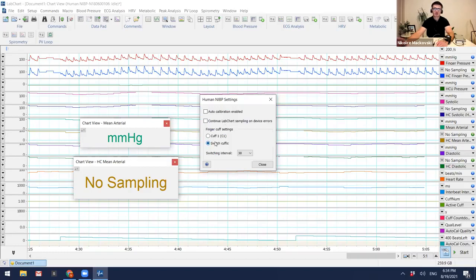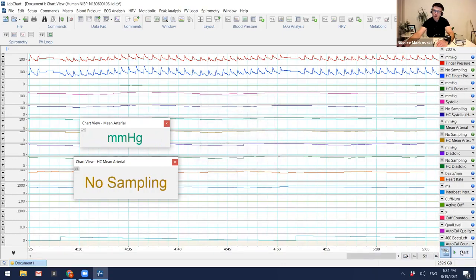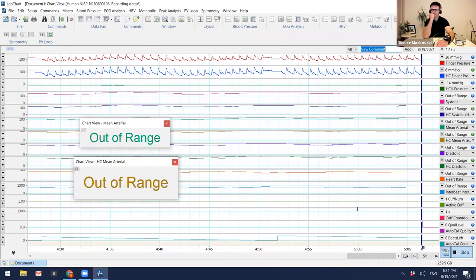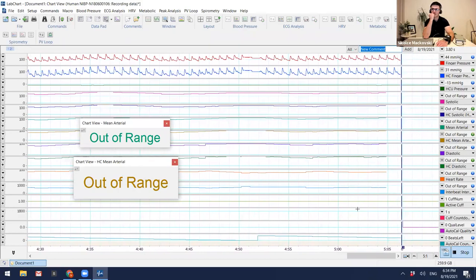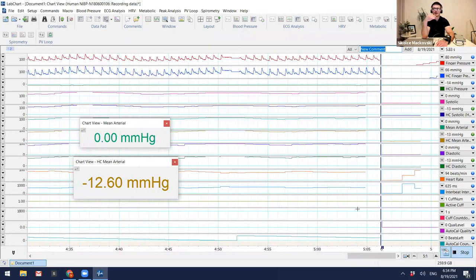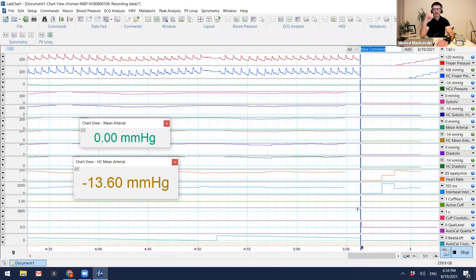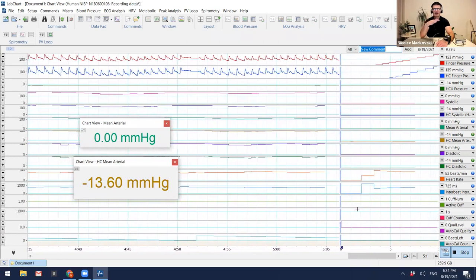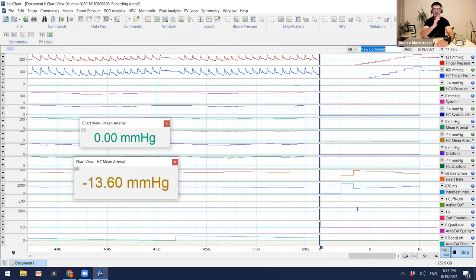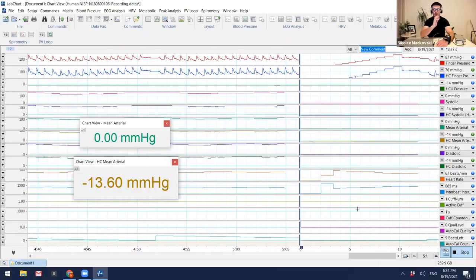Here, the finger pressure is in switching mode. So here I have a switching interval of every half an hour. Even though I've only got one cuff connected here, what I should have done was click on cuff 1. But if I have a second cuff, that way I can switch from one cuff to another. As I don't have autocal enabled, what you'll notice is when I press start again, we're not going to get any more autocals at all. So it's going to be a constant blood pressure reading.